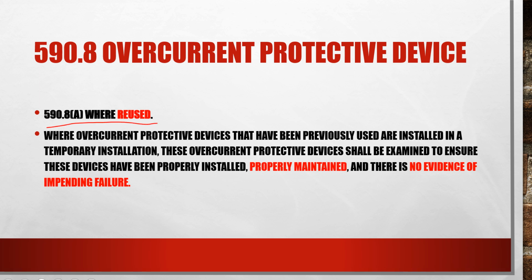It says where overcurrent protective devices that have been previously used are installed in a temporary installation, these overcurrent protective devices shall be examined to ensure they have been properly installed, properly maintained, and there is no evidence of impending failure. Whenever we think about our temporary installations, temporary equipment, and temporary poles, we often use these over and over again. They get used at one job, we take them up, we move to the next one, we may store them somewhere, or somehow we move them from place to place. So there's a lot of opportunity for damage. Why is it no crime? Again, a lot of times that's to save costs. Why build the temporary pole new every time? So it's no crime for us to reuse these temporary overcurrent devices that are in our equipment.